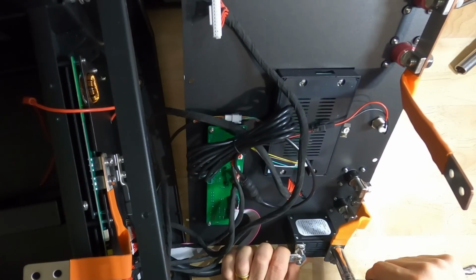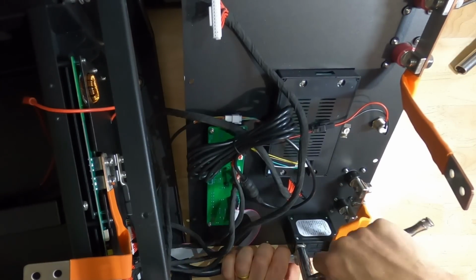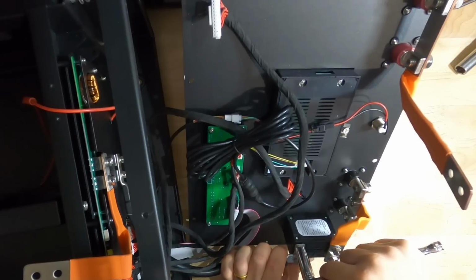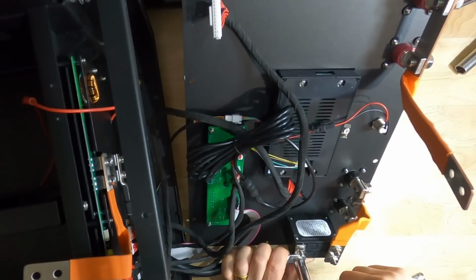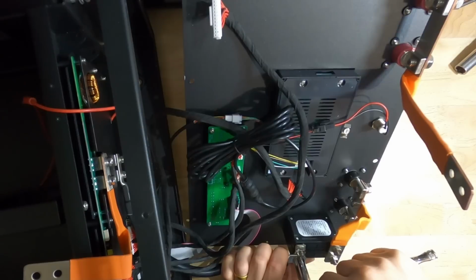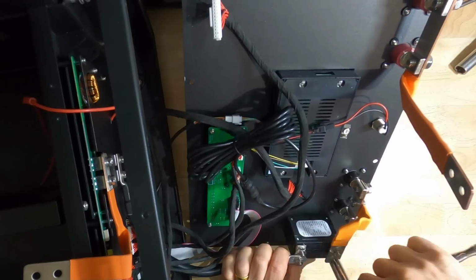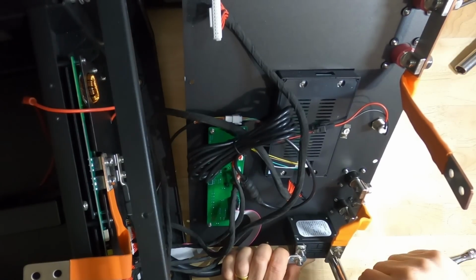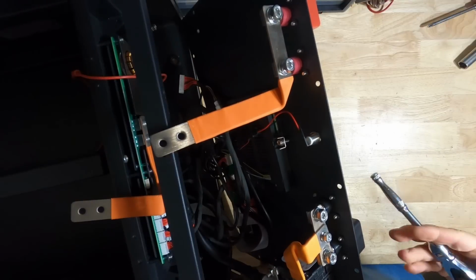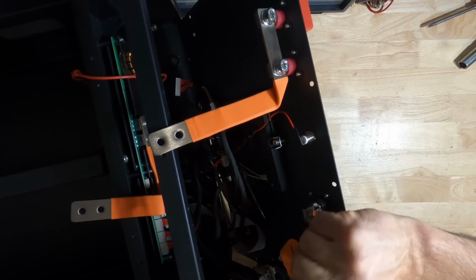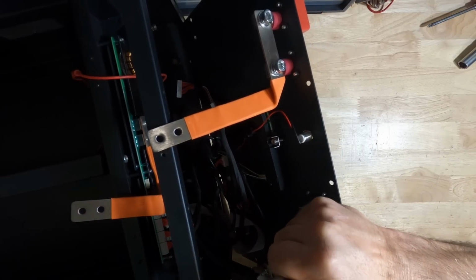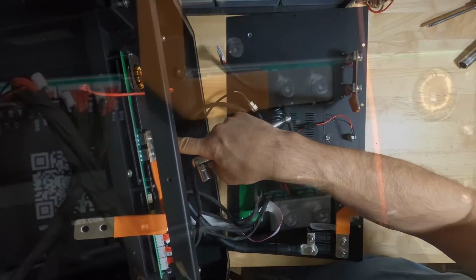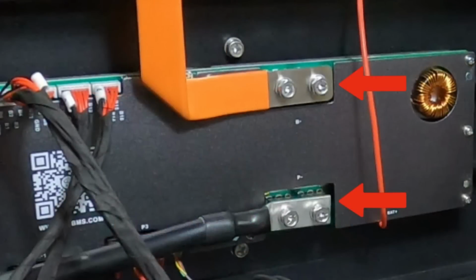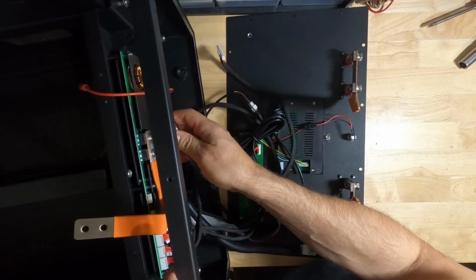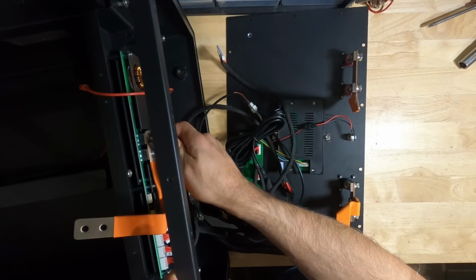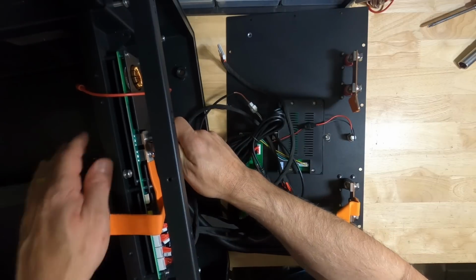Wow, especially on this breaker, I had to do like 6 turns on this. I'm actually surprised how loose these were. Make sure the M6 is tight there too, and also check these M6 on your BMS, B- and P-. Oh yeah, look at that, they're pretty loose.